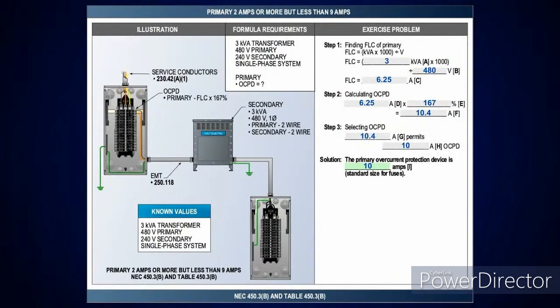All right. Now, this one here is a 3 kVA. This is where the primary is 2 amps or more, but less than 9 amps. Now, if you look there in the table, you're going to see current less than 9 amperes. Okay, it's going to tell you take it at 167%, but I'm going to point out here there's no superscript 1 right there. See that? Okay, so that means I'm going to drop down.